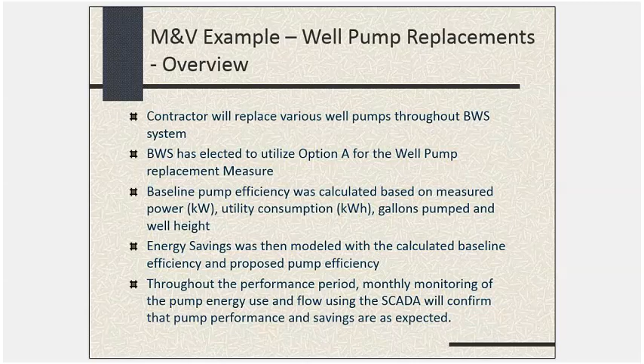Here's another example, going into the calculation detail a little bit more, where they talk about using a spreadsheet tool to calculate the existing pump wire-to-water efficiency using measured pump power and recording the flow from the SCADA system using the following formula.